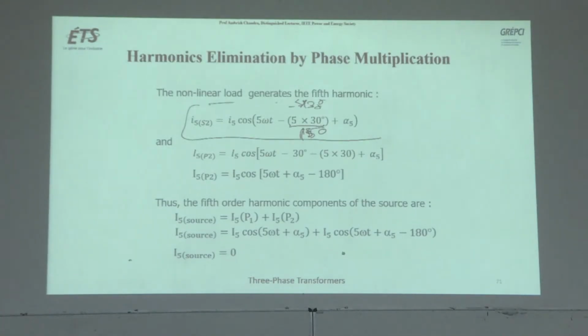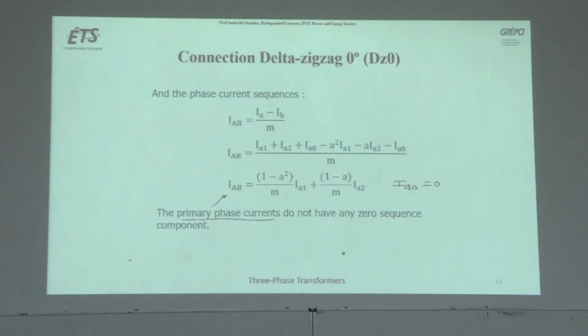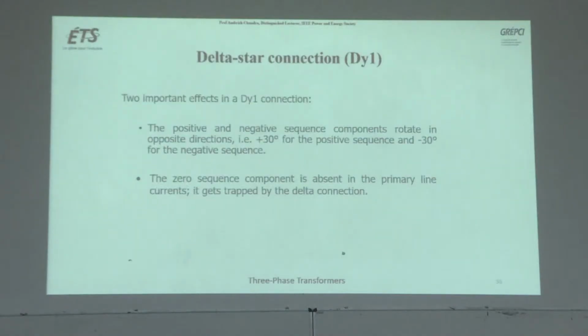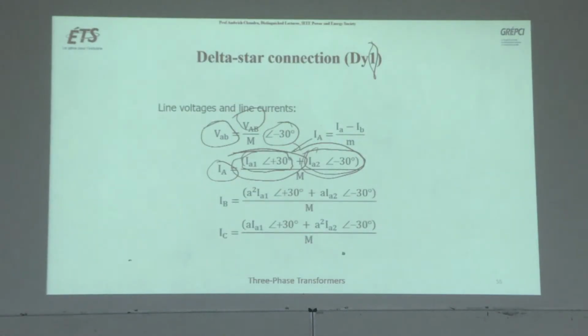Now when we bring this to the primary side, this is the secondary current. What we saw for the DY1 transformer is that the 5th harmonic is the negative sequence. Let us go and see DY1. 5th harmonic is the negative sequence, with minus 30 degree phase shift. So from the secondary current, when the 5th harmonic comes to the primary side, there is a minus 30 degree phase shift.